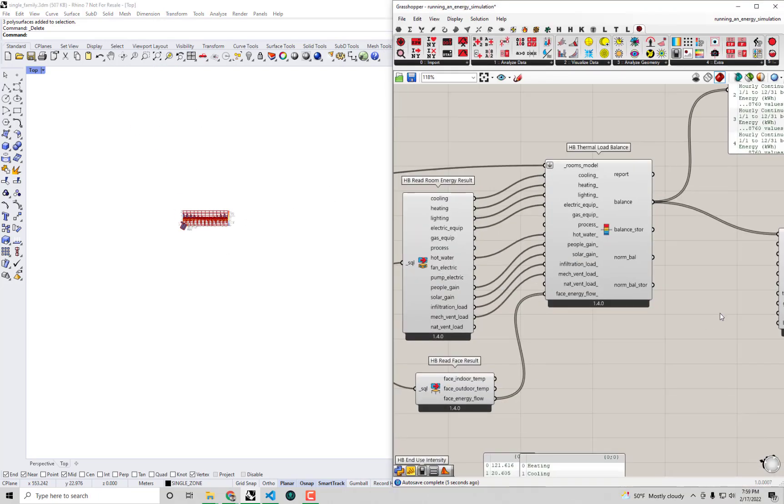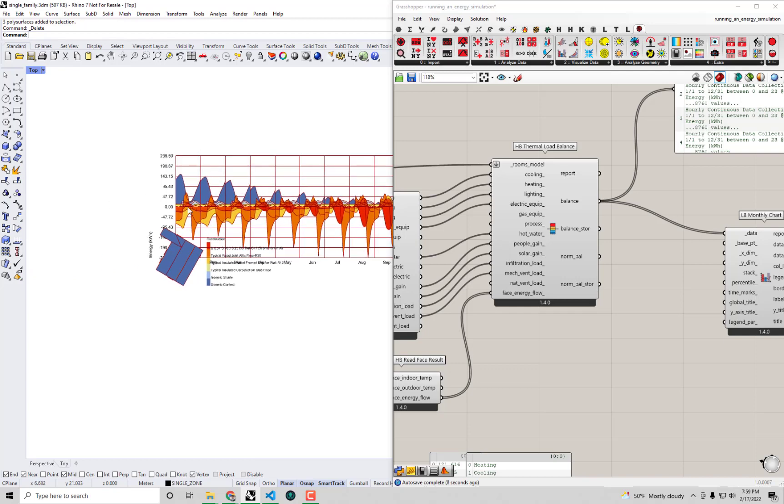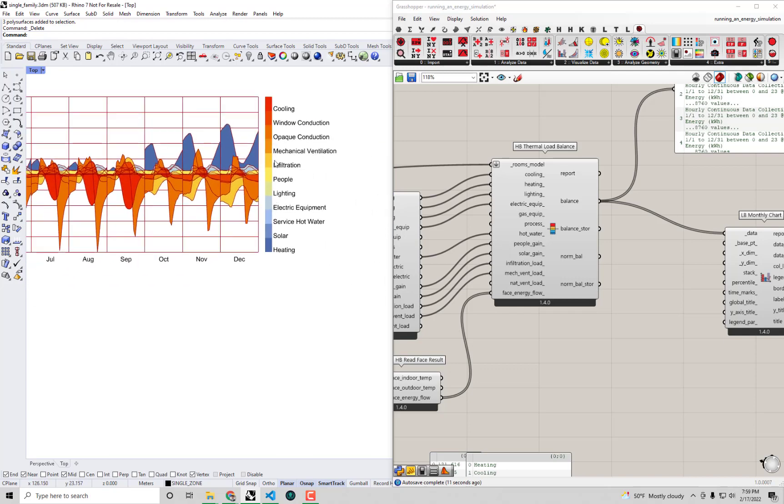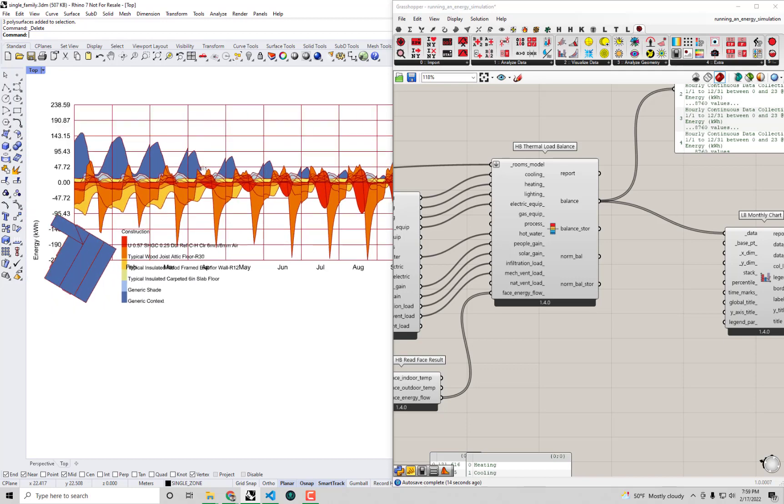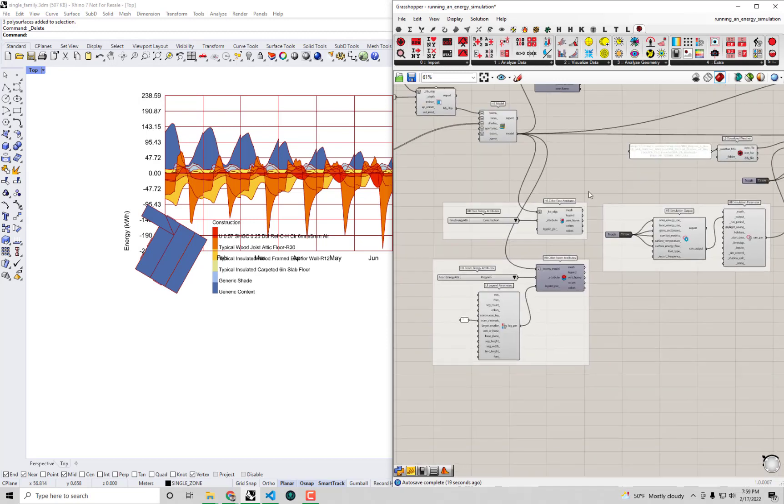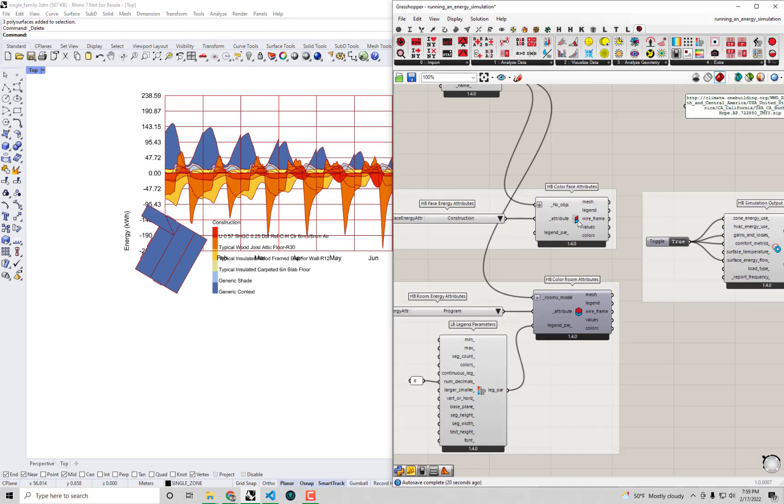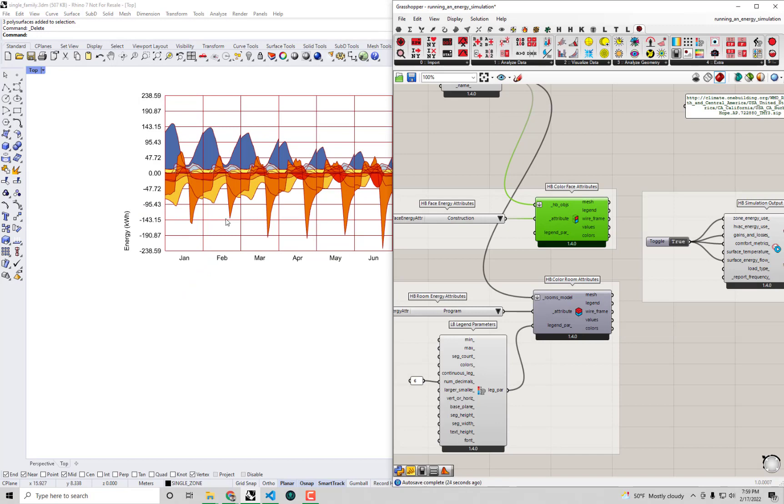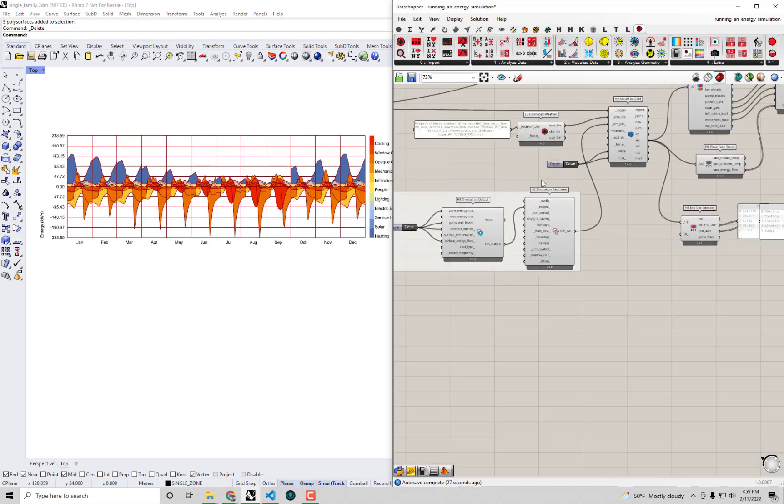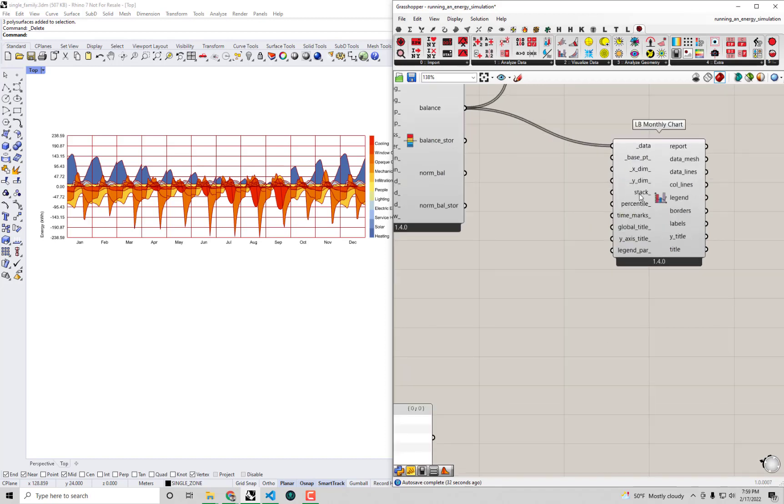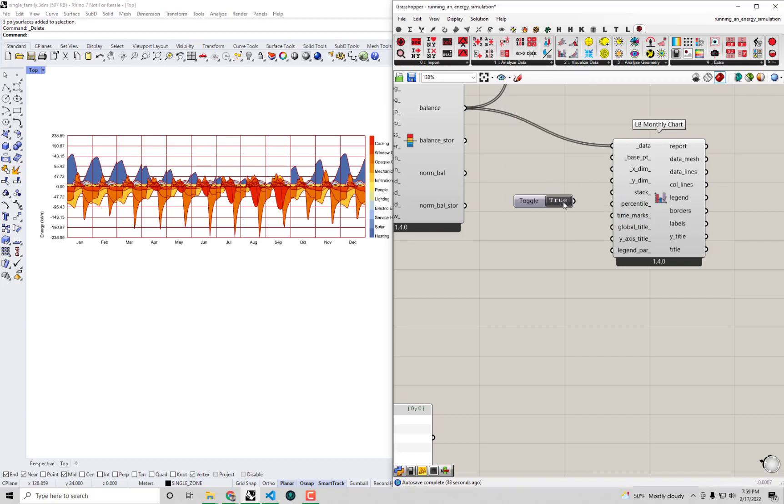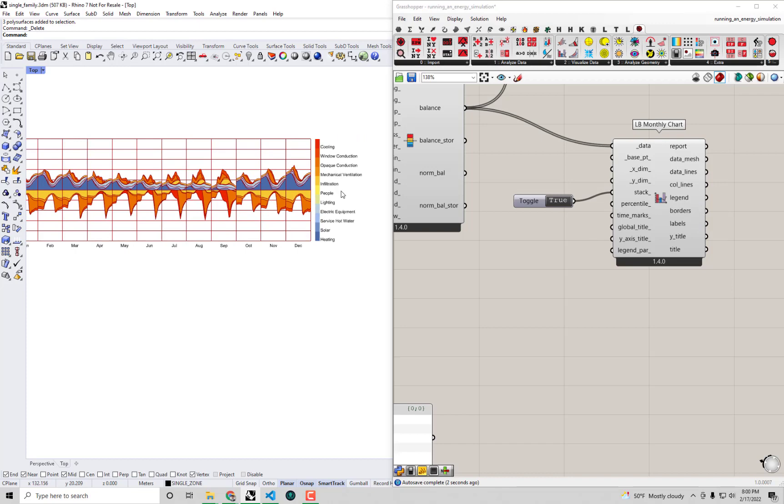And you'll see out of this component, you'll see that we get a balance out of this component, which is just a list of data collections. But in this case, we have one data collection for each and every term of the load balance. And a really nice way that we can visualize these terms is to connect them up to a ladybug visualization called the LB monthly chart. So I'm going to drag and drop this LB monthly chart on the canvas here. And I'm going to connect up the balance data. And you'll see if I go over to Rhino scene in top view, we get a pretty decent view of what's going on here. We have all these terms for cooling, window conduction, ventilation, but they're kind of all previewing on top of each other here. So I'm going to go over to the building here and turn the preview off on our color face attributes. And in order to make sure that each of these individual terms of the load balance aren't showing up on top of each other, I'm going to set this stack input of this monthly chart to true.